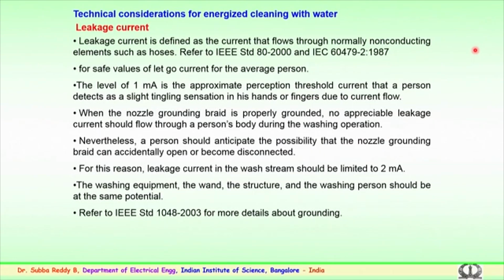We look into the technical considerations particularly for energized cleaning with water. What are the technical considerations which can be looked into apart from the quality of water, the measurement of resistivity, the measurement of conductivity or the addition of solvent, and so on? One of the important aspects is the leakage current. The leakage current is defined as the current that flows through normally non-conducting elements such as the water hose and the pipe.